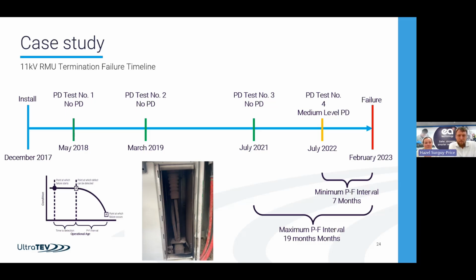The good bit about PD is that it tends to trend. It tends to start small, as you saw, that small arc, and it will progress over time. So you generally get a warning period, and that warning period is normally substantial. But it isn't always. It depends exactly where it is in the levels of stress around that part of the insulation, and what's caused it, especially if it's something that's moved and that's then caused it to kick off rather than a static portion. You tend to get slightly less time. So the key bit is it's got to fit with your risk profile. What you're looking for is to manage the time between being able to detect it and failure, and make sure that is reasonable.